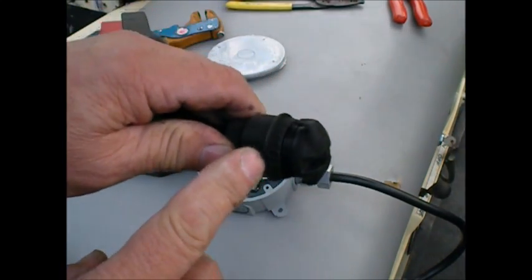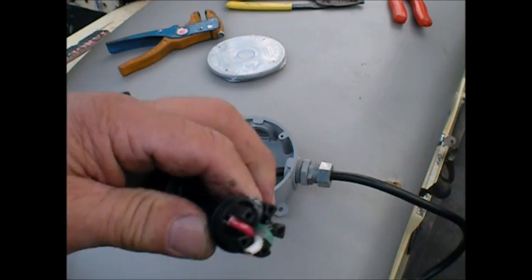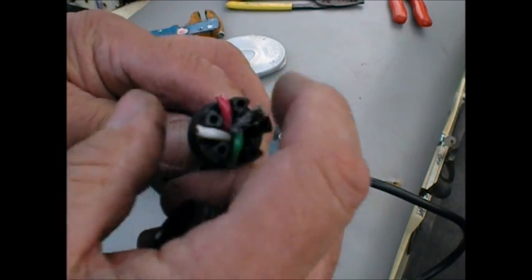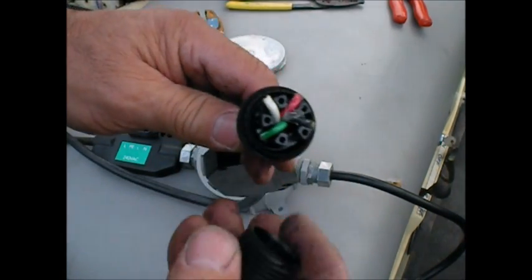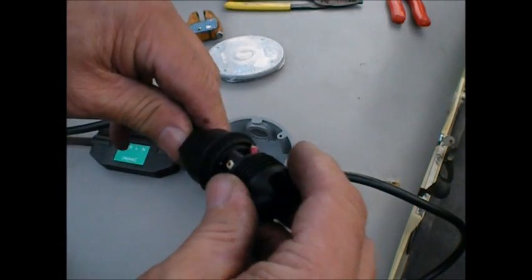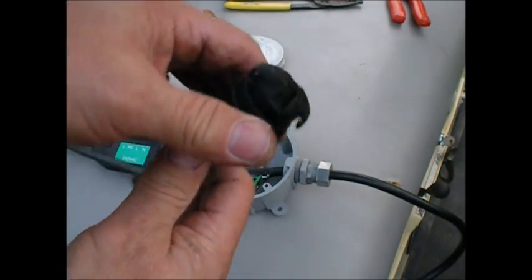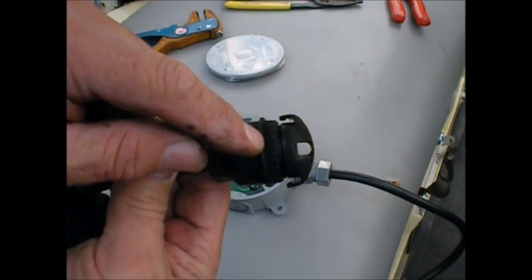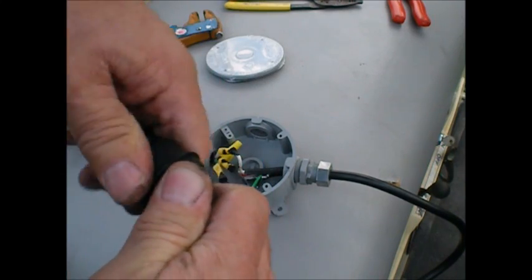On the other end here — I don't know if anybody has used one of these yet — these are the Enphase end cap termination sealers, I think they're called. What this looks like inside: you just take your four wires, get your neutral, a ground, a hot and another hot, fold them over these little ears for the end of these Enphase cabling system. Just clamp this on, push it over, screw this on. You can see these little ears — they lock into these ridges here on the bottom piece, and you just turn it. And that's how you terminate the end.